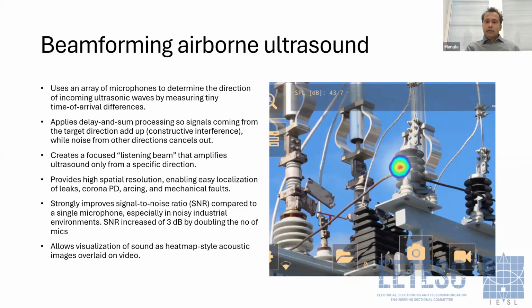That's the principle behind the operation of an ultrasound camera. As I said, the number of microphones helps to increase the resolution and the sound signal to noise ratio. When we double the number of microphones, we can approximately increase the signal to noise ratio by 3 decibels.